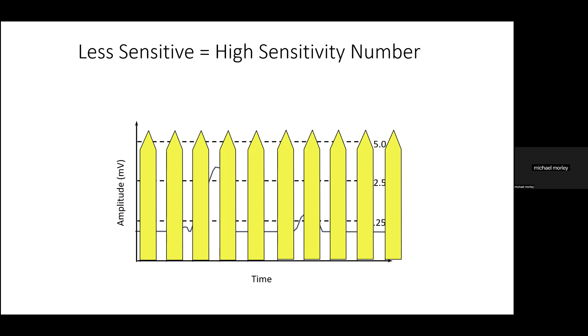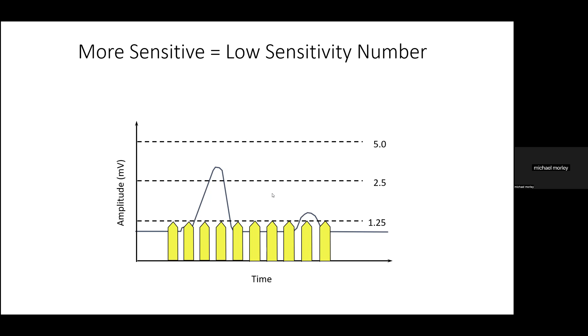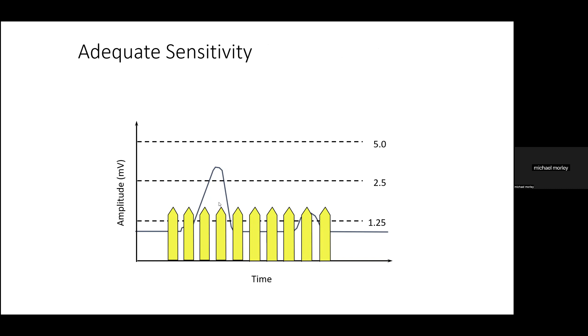Conversely, if we make the system too sensitive by setting the sensitivity too low, then yes, we can see what we want to see, intrinsic ventricular activity, but the device is going to get confused by seeing other things such as the T wave, and you can get what's called T wave oversensing, which can inhibit pacing. Get the sensitivity just right, and the pacemaker has a simple job because it's only seeing what we want it to see. In that way, it can sense intrinsic activity and we get back to our demand pacing.